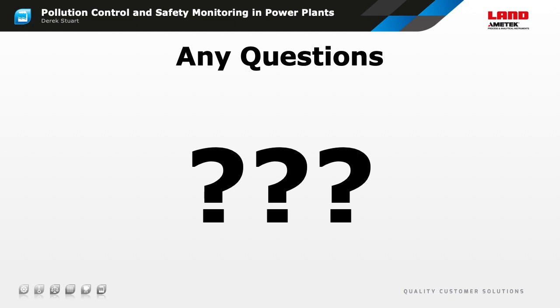And some US EPA rules, for example, the mercury and air toxics, the MATS rule, have provision for either a PM-CEMS or an opacity monitor, and you've simply got different quality assurance rules to take care of depending on which way you go with that. In most cases, it's better to choose an opacity monitor if you have the choice, because it avoids the entire need for a correlation test, and that's a significant saving both in the initial setup and calibration and in the ongoing quality assurance and quality control. Quality assurance for an opacity monitor is much, much easier than it is for a PM-CEMS.